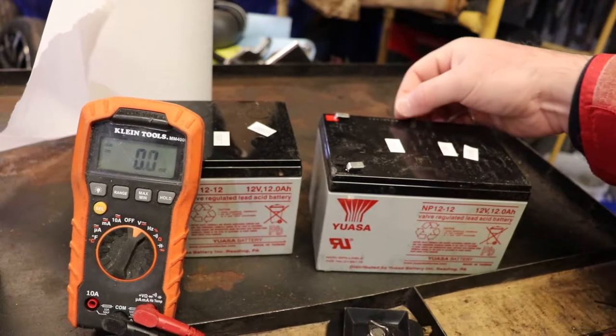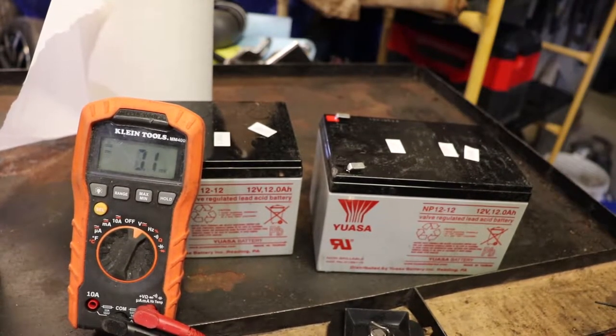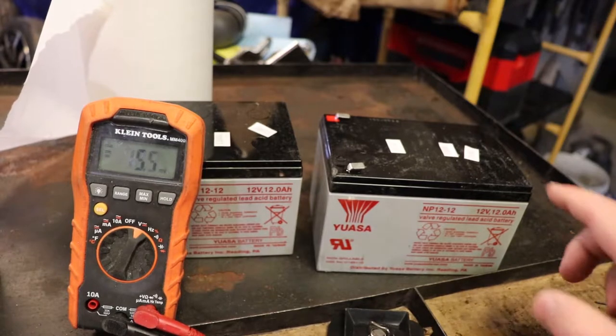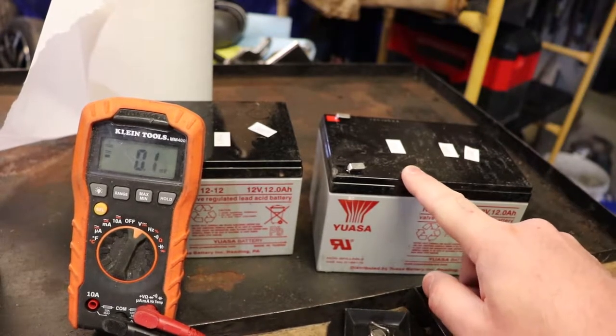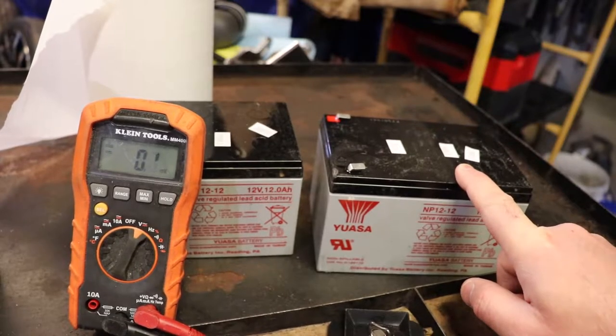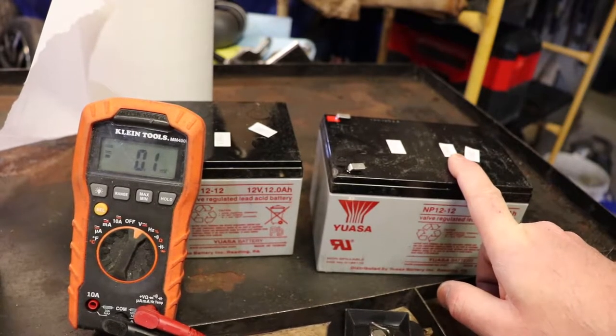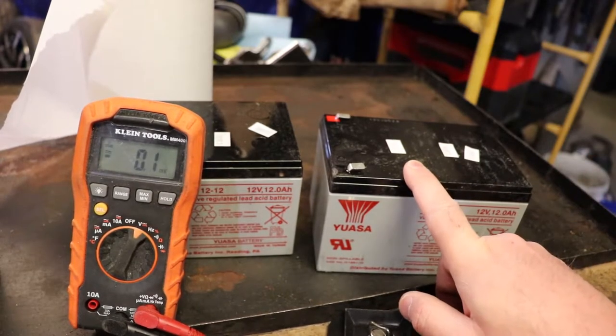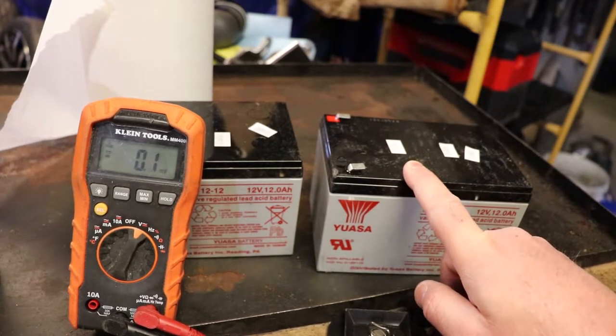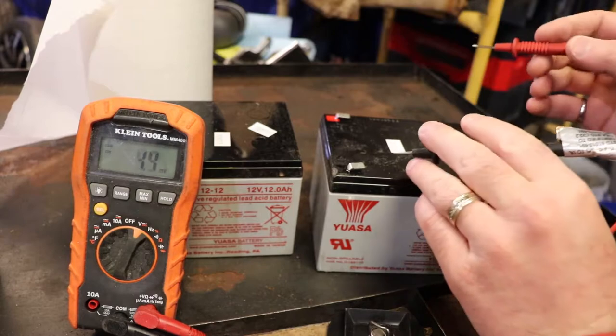There's a number up here: 1903-05, so it would have been built in March 2019. They've got a sticker for each time they've been charged - every six months they charge the batteries, and if they find them too low a voltage they scrap them. It was charged three times and hasn't been charged since March 2020, so that's a bit over a year ago. I checked the voltages and they seem okay.